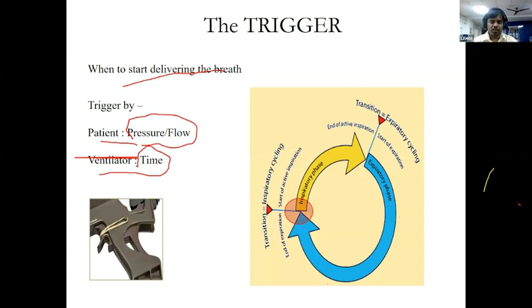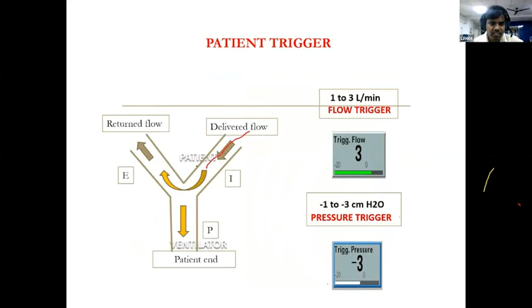What is patient trigger? You see the diagram here. When we are delivering the flow and the patient's return flow comes, the patient will trigger, and this should be assessed by the ventilator. So you should know the trigger sensitivity in the ventilator setting. I'll show the ventilator setting here. It should normally be -1 to -3. Why are we keeping it? Suppose I'm triggering, the ventilator should assess my trigger and deliver properly. That is why they kept the normal value of -1 to -3 centimeters.